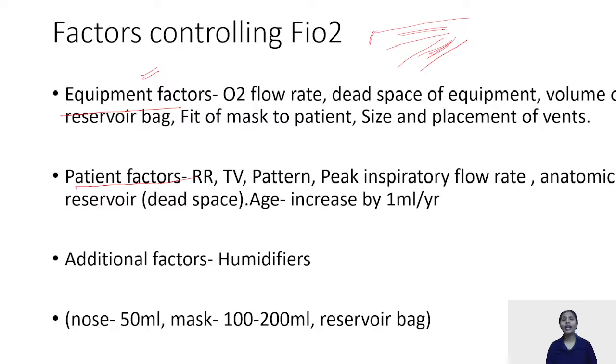And lastly, we have vents. We'll be coming to this: in various oxygen therapy devices, we have certain vents which are present for the exhalation of the CO2. But the same vents can also lead to dilution of the fresh gas by entrainment of air if the flow rates of your oxygen therapy device do not meet the peak inspiratory flow rate of the patient. Then we have patient characteristics.